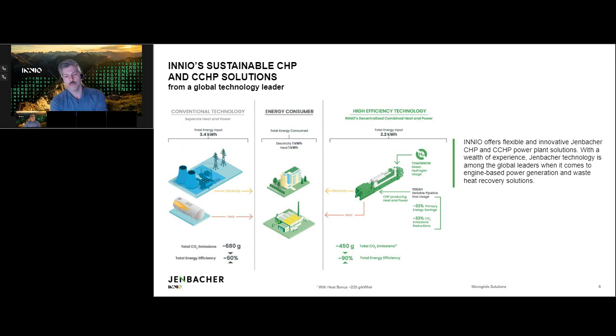As far as a basic sustainable combined heat and power application, this is an example of a typical application for an energy consumer, showing the high efficiencies of capturing both the electrical power and the thermal energy off of the engine. This gives us somewhere in the range of almost 90% total energy efficiency, which can be derived in terms of hot water, low pressure steam, process steam, however you want to use that heat. We can adapt a system that will be quite effective in the Type 6, and really in all of the engine types, but we tend to focus on the Type 6 for this kind of application, just because of its power node.